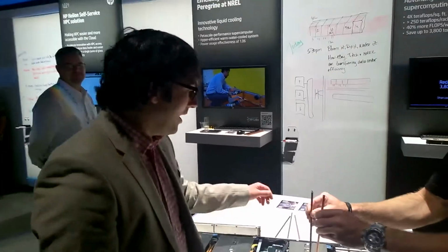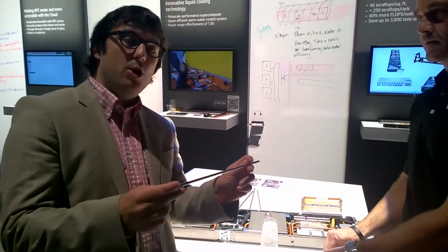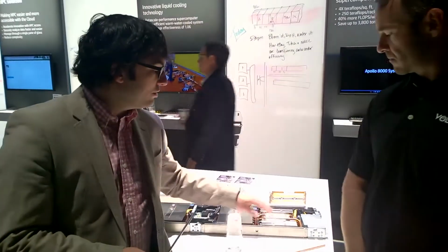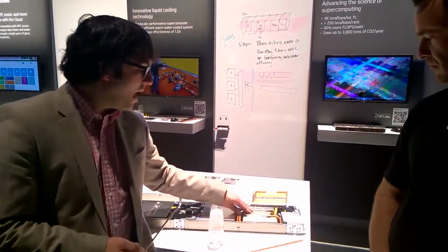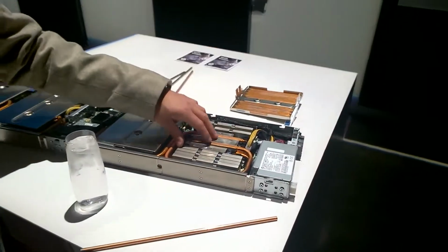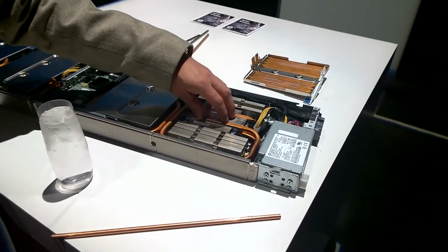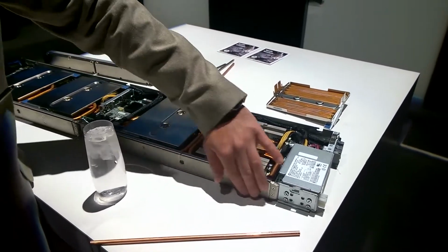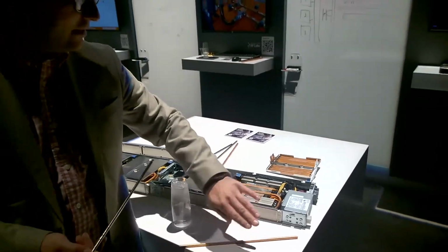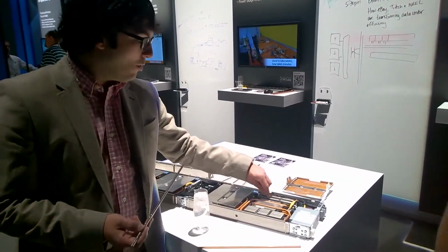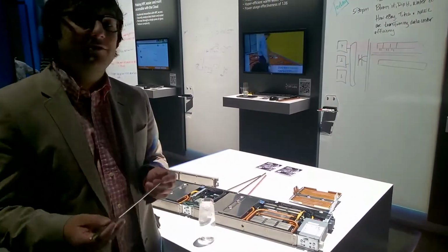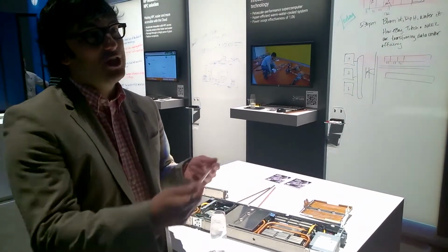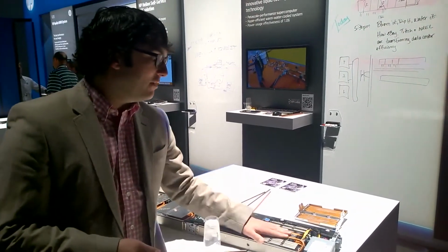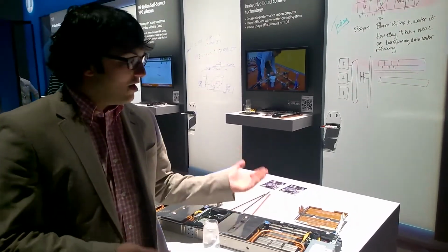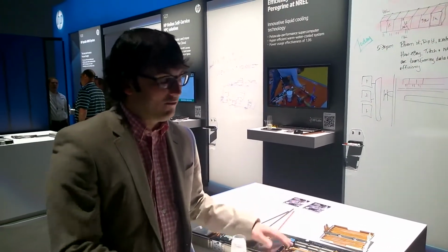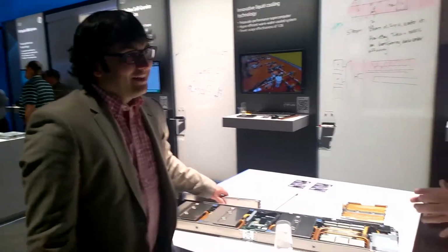There you go. So a heat pipe is basically a device that has a hollow core and works as a phase change system. What we use here on the Apollo compute tray are a set of heat pipes where the tiny amount of water vapor in the heat pipe will evaporate as it captures the heat from the processor, travel as water vapor to the thermal contact plate here, and as the heat gets extracted, it goes back into liquid form and travels back. So vapor, liquid, vapor, liquid. It's a passive device. There's no pump. It doesn't break. Super efficient, and with a cost structure that allows us to give you the experience of an air-cooled server, but with the thermal performance of a liquid cooler. That's outstanding.